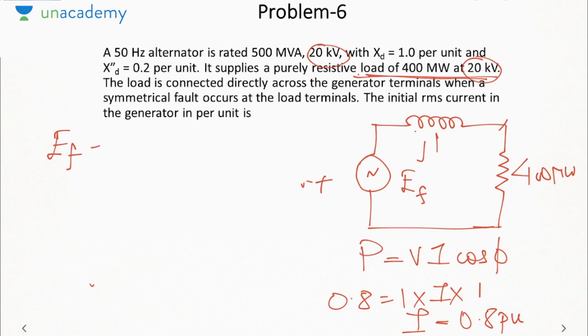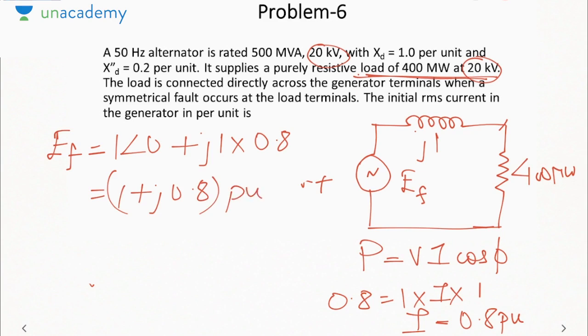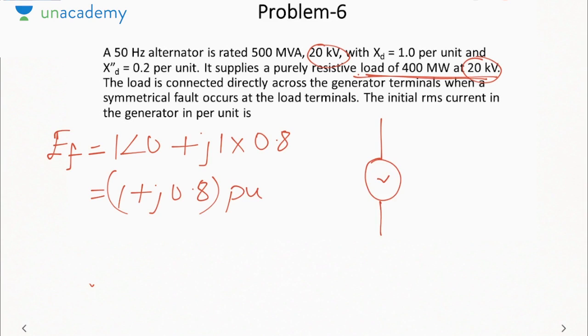Vt is 1 angle 0. Plus j into Xd, that is 1 into j0.8. This will be 1 plus j0.8 pu. Now what happens when the fault occurs? The entire current will go into the fault and we will enter the subtransient region. So how will my system look like?